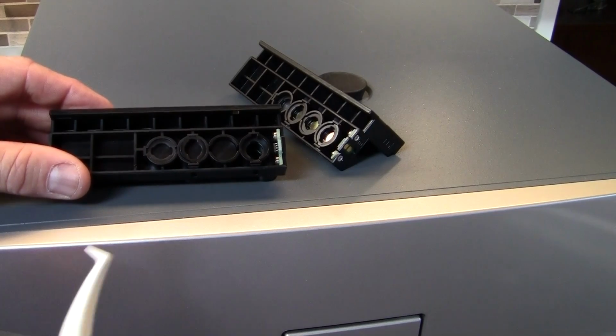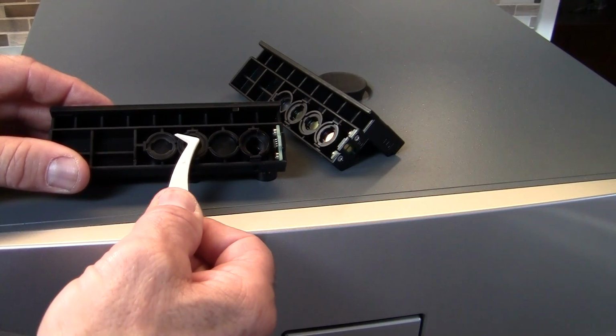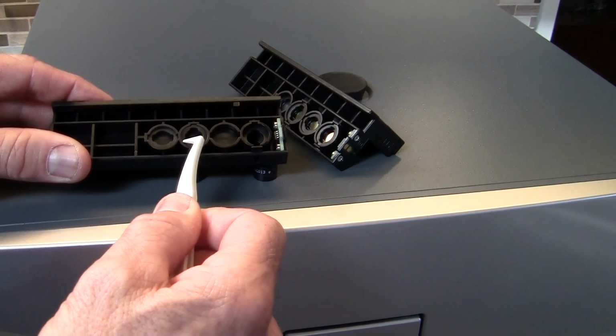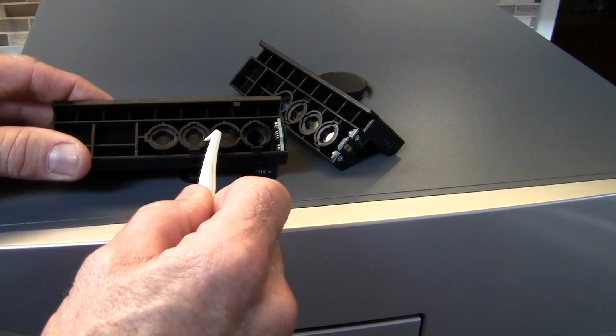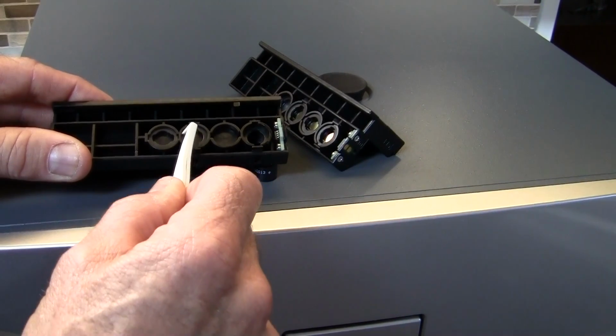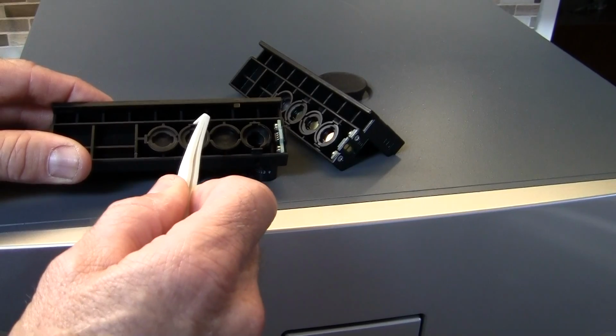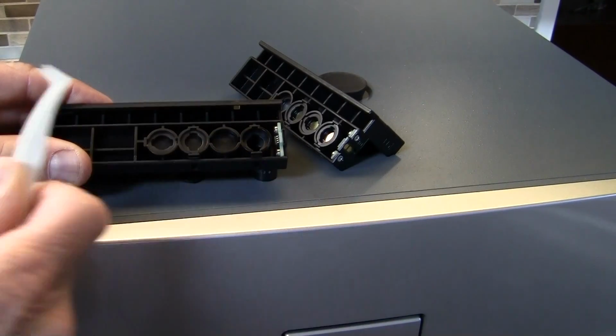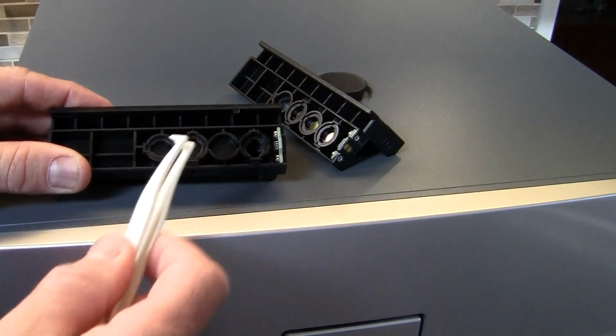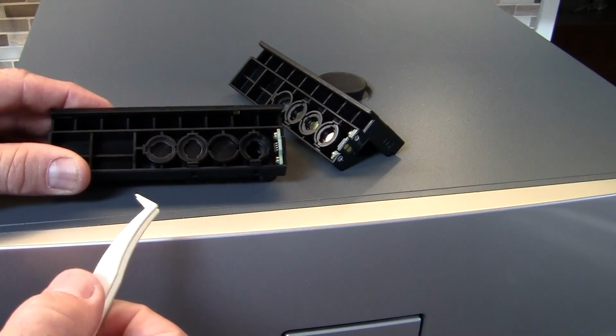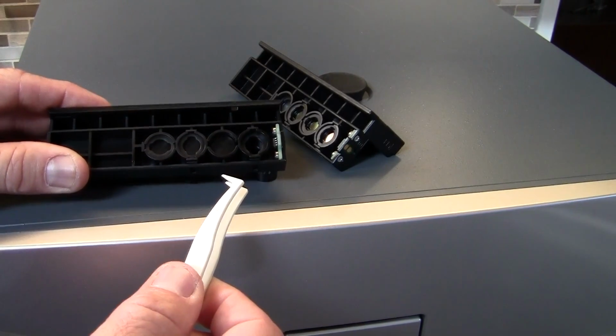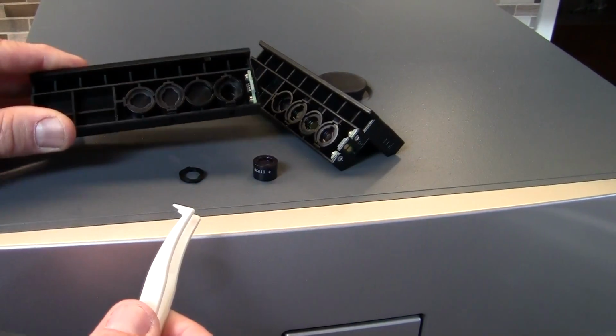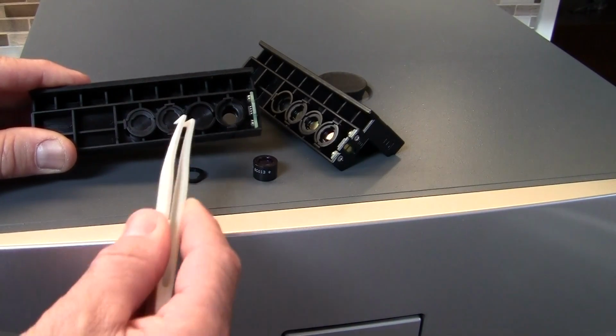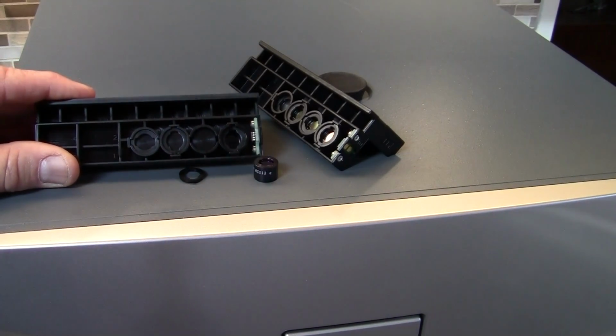You can guide the O-ring into position and then use the tweezers to help press it into place, like so. Just run the pointed end around the outside to make sure it's seated properly, being careful, of course, not to touch the filter if there's one in place. In this case, I'm just doing an example on one of these black plastic plugs that are used where filters are not put in a particular position.